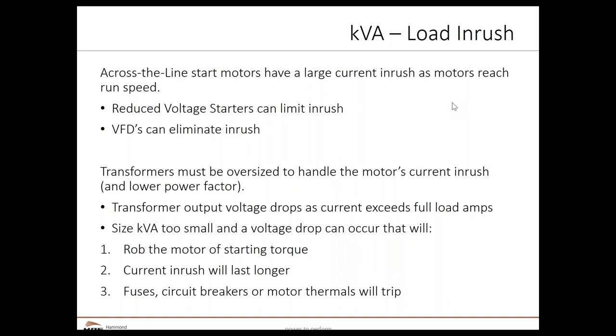What we're worried about is that when this inrush occurs and it's trying to give the motor extra current, any time the output current exceeds the transformer's rating, the output voltage starts to drop. The more you exceed that current, the more voltage drop you have. When that motor starts, the output voltage will drop, which robs the motor of starting torque — it doesn't have as much torque to turn the load, meaning it might take even longer to get up to speed. That's actually how a reduced voltage starter works, but we don't want to unintentionally use a transformer as a reduced voltage starter. The longer current inrush can cause fuses, circuit breakers, and motor thermals to trip, resulting in nuisance tripping.